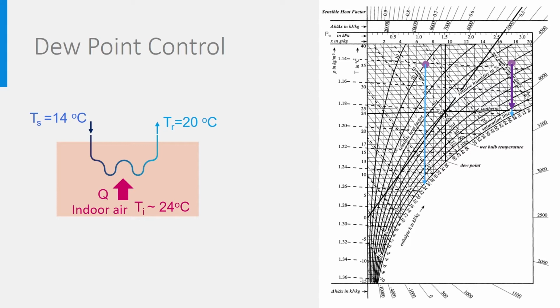Air in a room is not still, it is moving all the time. There is hot ventilation air coming in and being mixed with room air. There are airflows along the cooling panels. These airflows come in contact with the cold pipes in the panel and therefore cool down to 15 degrees, for example, before being mixed again with the room air. 15 degrees is below the dew point, therefore condensation will take place.